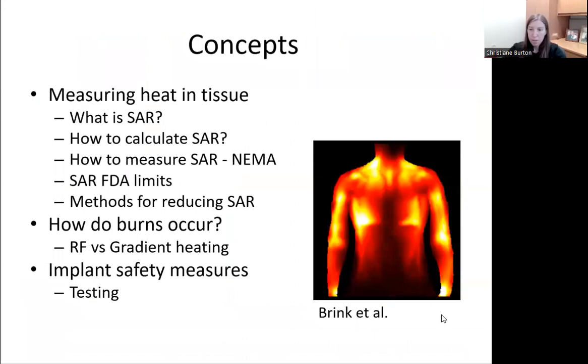Okay, so here are the concepts that we will need to go over in terms of thermal injury. The first is a type of measure of tissue heating known as the specific absorption rate, otherwise known as SAR. We will go over how to calculate SAR, what the two permitted methods are for measuring SAR, the FDA limits, and methods for reducing SAR. In terms of implant heating, we will go over thermal injury from RF waves and gradients. Then I will talk about implant safety measures and how different implants are tested for heating. Then I will end the talk by showing different types of burns and what causes them.